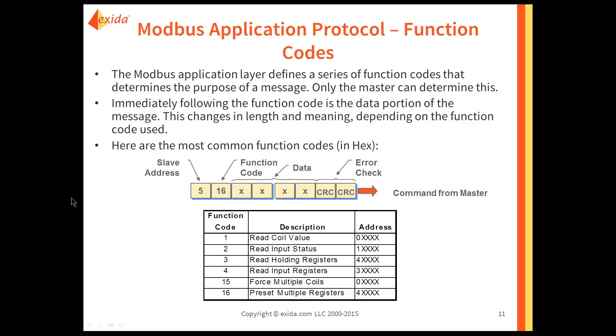A rundown of how the Modbus application works at the functional level: when a master makes a request of a slave, if the slave device has a unit address, it puts that into the message so the slave knows which to answer. Then it puts in a function code — the instruction of what the master is looking for. It could be a read, a write, a read or write of one, a read or write of many, or a program function. It all depends on what that function code is.